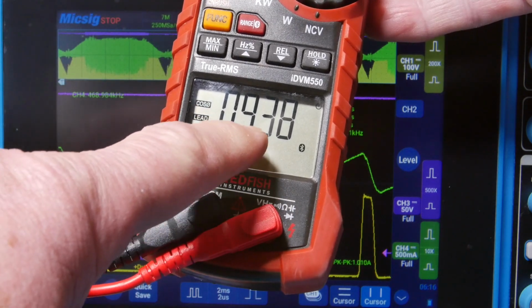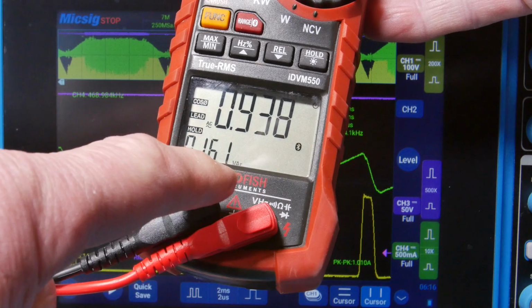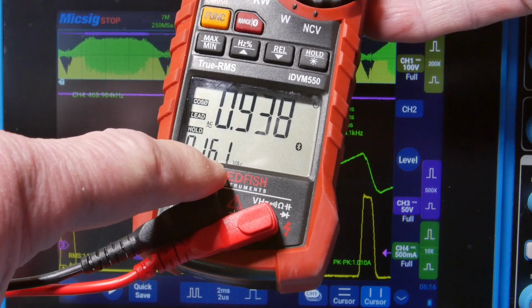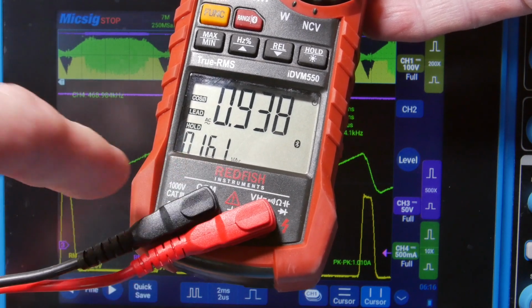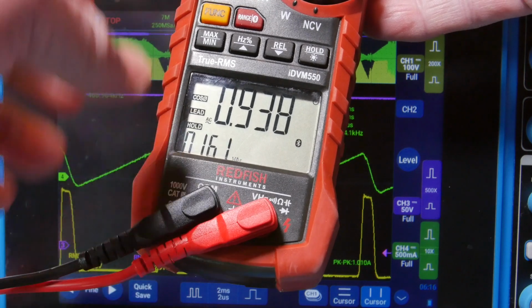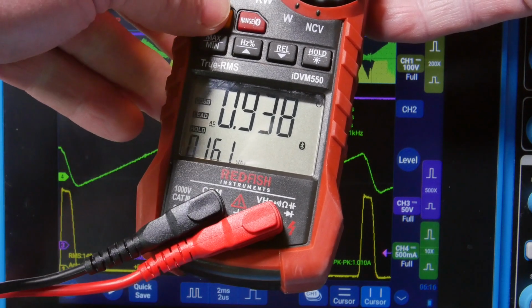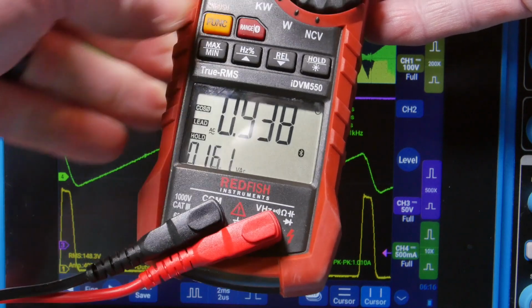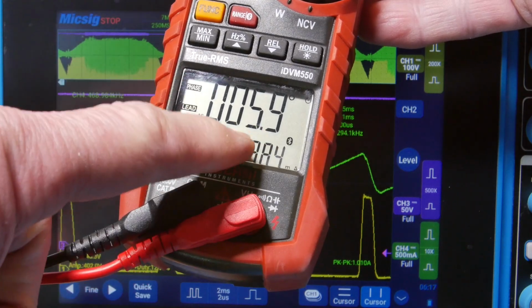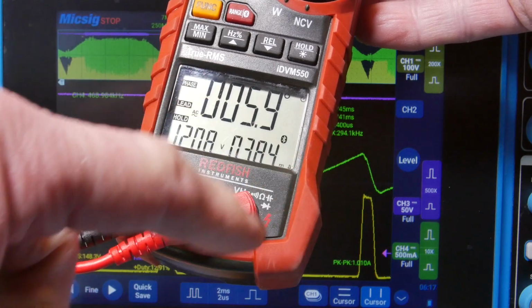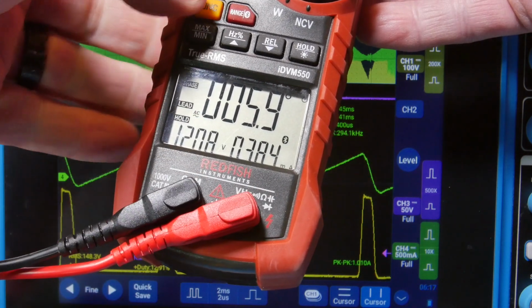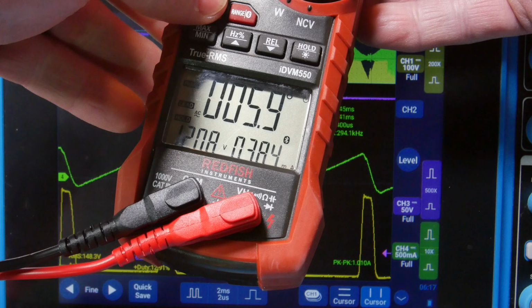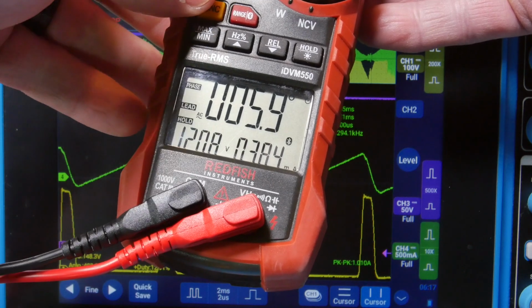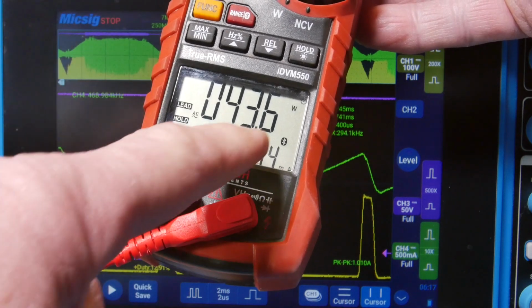And this is why the power factor is 0.938, so 0.94. There's only 16 VAR, so with all that power, we only got a little bit of reactive power. The phase between the apparent power and the real power is only 5.9 degrees. So pretty nice power factor. And this is a light load, it should get better with higher load.